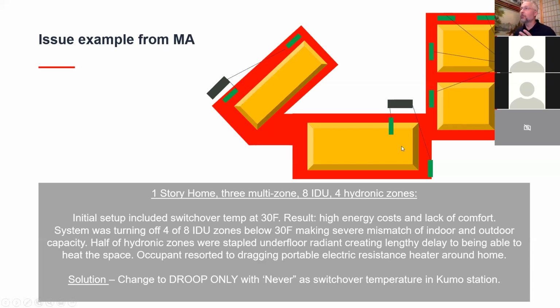One of the things that was kind of wacky is that at 30 degrees it would shut off and turn on the hydronic zone, but it would turn off one, or in some cases half, of the indoor capacity of the outdoor multi-zone system. So the multi-zone is like, well, one of my indoor units wants to keep running hard, but the other one's totally off. There's a mismatch between the indoor and outdoor coil size and the capacity of the compressor, so it would generate a fair amount of cycling. On top of that, the radiant would come on, but in 2 of these zones it was baseboard, and in 2 of the zones it was underfloor stapled. If there's anything we know about underfloor staple, it takes a long time to heat up the floor to a point where it can deliver heat into the space. Depending on the circumstances, it could be a day or more.